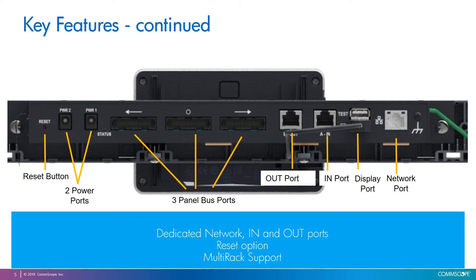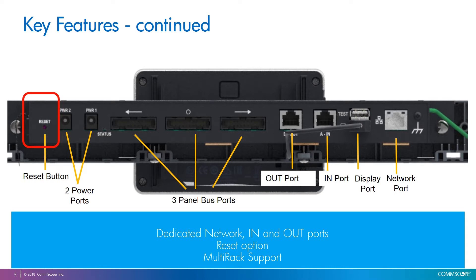Here we see the InVision Controller X from the back. On the right side we have a dedicated RJ45 port for network connection and two additional RJ45 ports for the in and out connections to other nearby controllers. On the left side we have a reset button. This lets you delete all information in the InVision Controller X and clear configuration, network, and security settings to factory defaults. There are also three panel bus ports which allow this new InVision Controller X to provide intelligence to up to three adjacent racks.